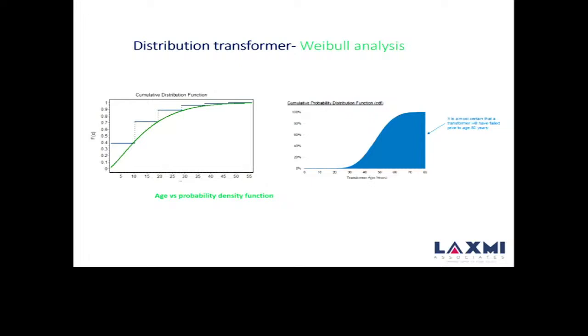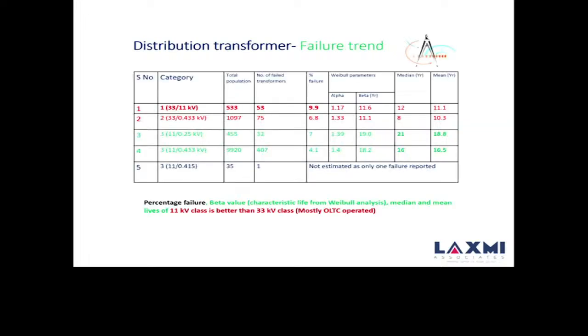That is the guaranteed life you can get from the distribution transformer in that system. Similarly, for transmission and generation, another study shows 50% failure here, so 45 years is the average life. It depends on whether it's distribution, industrial, transmission or generation - the mean life will vary. If we do this in our own system, it will vary too, but the study is good, meaning this much life is at least expected across the overall fleet.